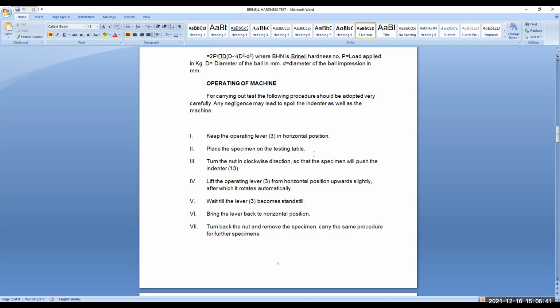Next, lift the operating lever from the horizontal position upward slightly, after which it rotates by its own weight automatically to the right position. Wait until the lever becomes standstill, and wait there for say 15 to 20 seconds, and then bring the lever manually to the original horizontal position. Turn back the handle in the anti-clockwise direction so that the platform goes down, and remove the specimen and carry out the same procedure for other specimens also.